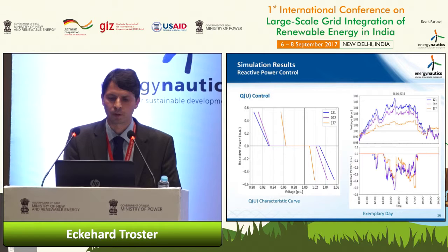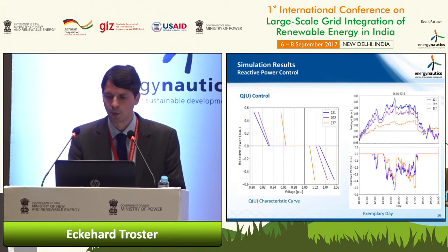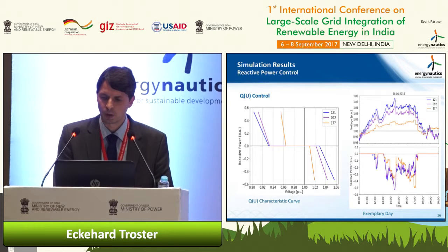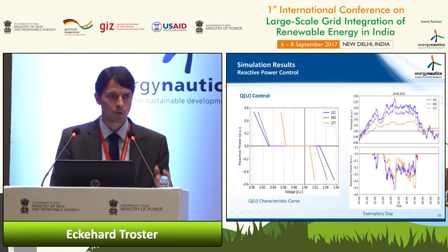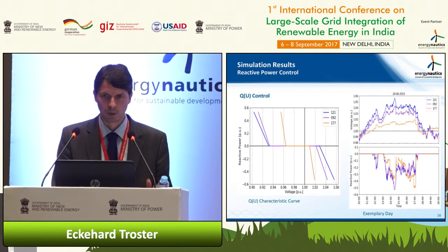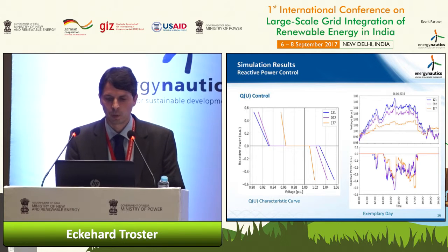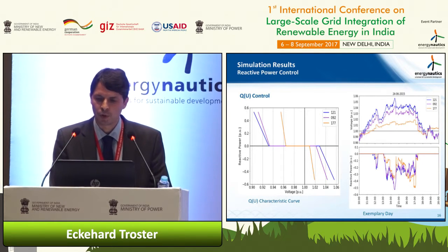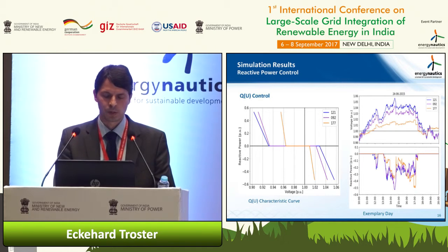This orange one here is a location which faces only lower voltages, shown here, and that's the voltage up here. Therefore, we asked it to act earlier, at lower voltage levels, in order to provide reactive power and support the system. Whereas these two, the bluish and purple voltages, are much higher, up to 1.06 per unit, as I mentioned earlier, and we implemented this characteristic for Q.